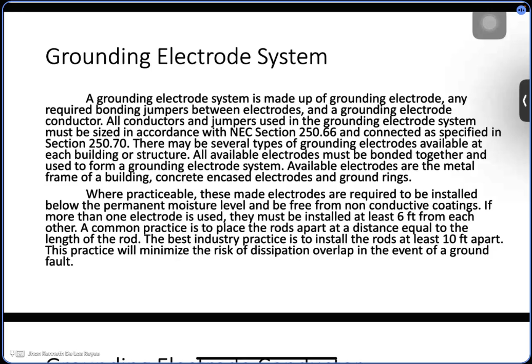In this part, under OSHA 29 CFR 1910.399, the grounding electrode conductor, or GEC, is usually copper since that's the best material. It may also be aluminum but with restrictions, so it's not always aluminum. Though it's used, it really has restrictions, and it cannot be spliced unless special methods are used, and it must be continuous with no breaks in the wiring.